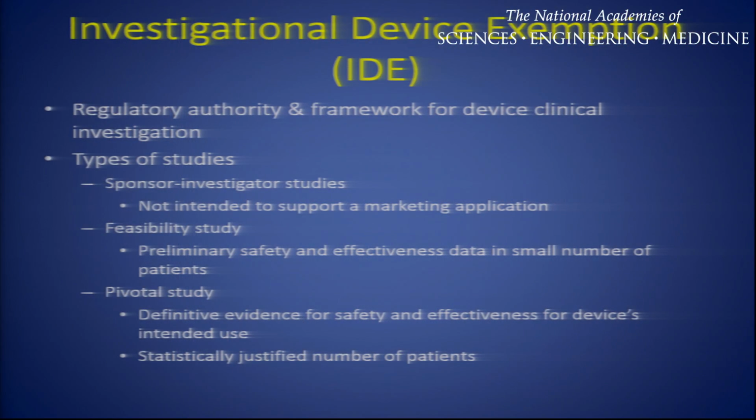Now I'll switch gears and talk just quickly about the IDE program. It's a regulatory authority and framework for device clinical investigations. There's a number of different types of studies. Sponsor-investigated studies, which are not intended to support a marketing application. Feasibility studies, preliminary safety and effectiveness data in a small number of patients, and these can be used to support a marketing application. And a pivotal study, definitive evidence for the safety and effectiveness for a device's intended use, which usually has to be statistically justified with the number of patients.